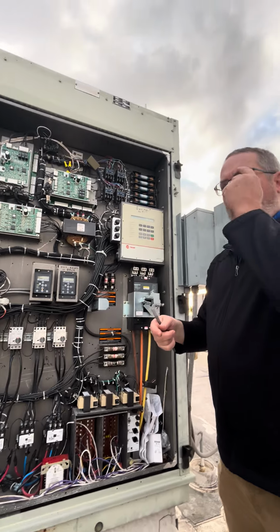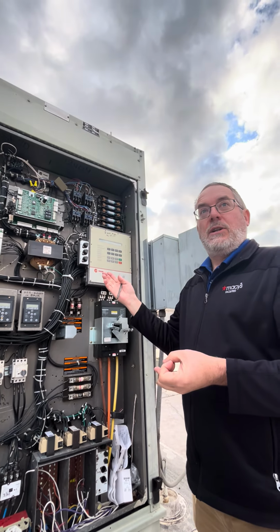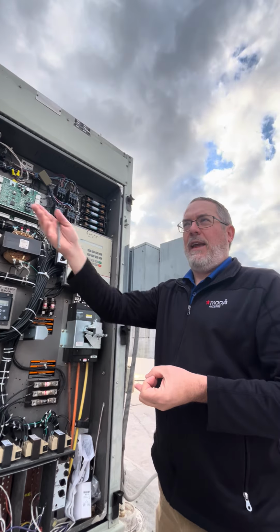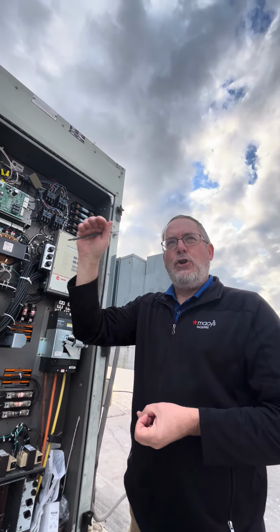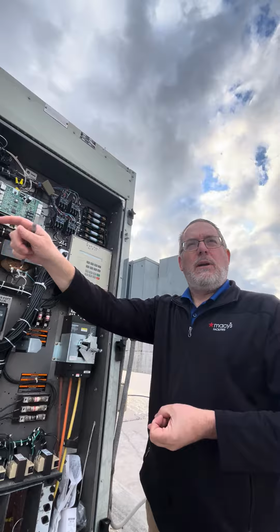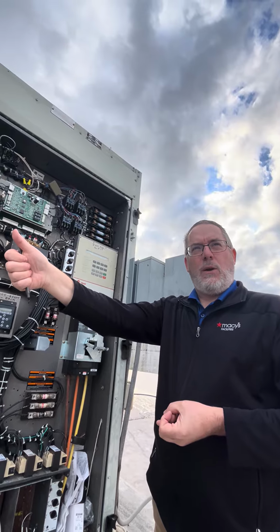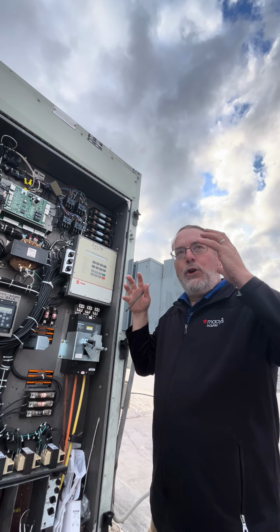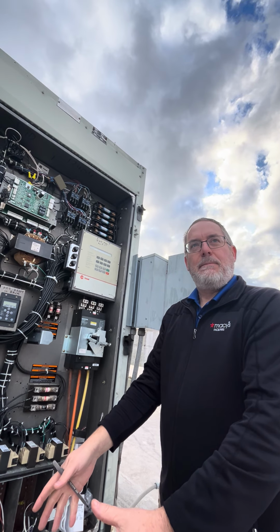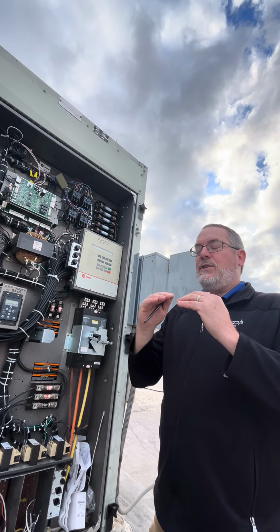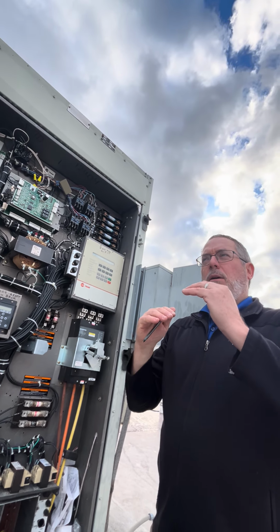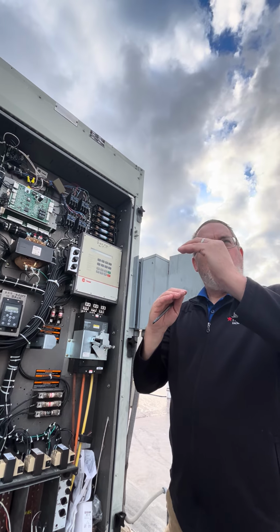Yep. And now I'm not using a lot of power on the unit because I'm only running maybe one stage of cooling. The fan's at minimum. I've got good supply temperature. I've got good dehumidification off that coil. I'm below dew point, and I'm not throwing all the cooling BTUs into that space. Now, if one stage of cooling doesn't match and the temperature keeps going up, well then that fan will start ramping up slowly.